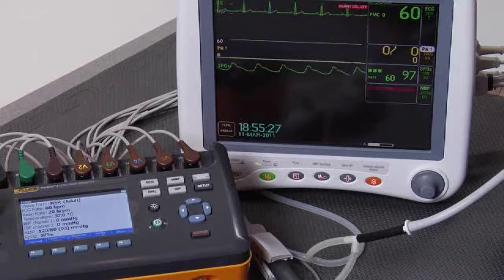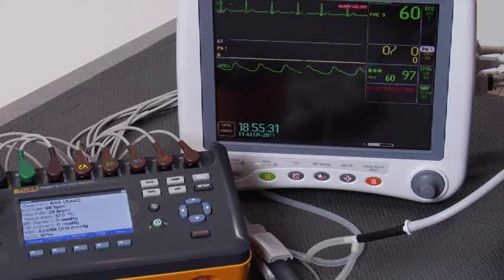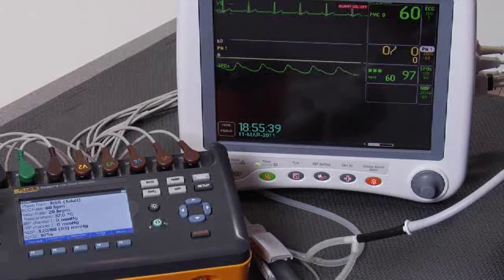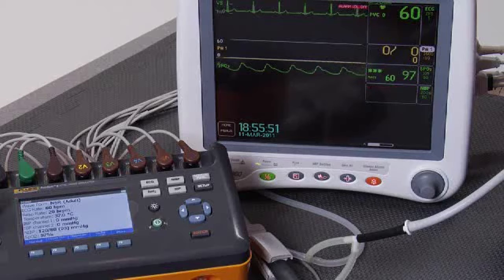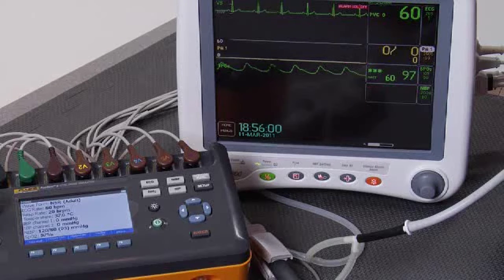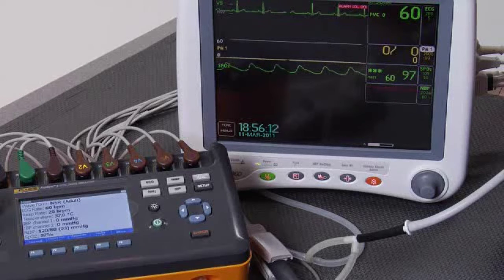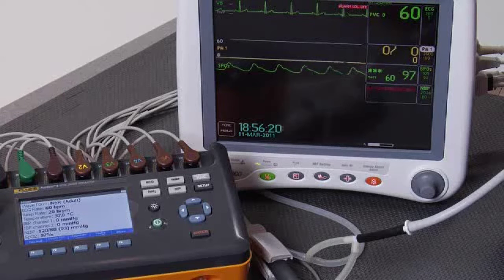So as I begin the test, we are already connected to the device under test. All of the connections have been made ahead of time, including the NIBP cuff. And we are going to zero our invasive blood pressure transducers on the patient monitor at the very first step, followed by a selection of a simulation of all coordinated patient parameters. We'll do hypertensive first, followed by normal, followed by hypotensive, in order to assess whether we have a performing patient monitor. We will compare the displayed values on the ProSim 8 against what's displayed on the patient monitor at each set of simulated parameters. Are you ready?